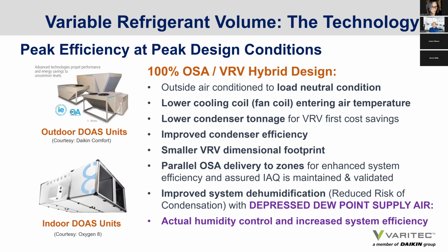So from an overall design approach and its advantage, what are those advantages specifically? Well, we can provide outside air conditioned to load neutral condition, 70 to 75 degrees, whatever you want, by using hot gas reheat. We can lower cooling coil, fan coil entering air temperatures, because the fan coil is now only seeing the temperature of the return air to the building, not a mixed air condition of the return with the outside air. Lower load on the fan coils means lower condenser tonnage and consequently lower VRV first cost savings.